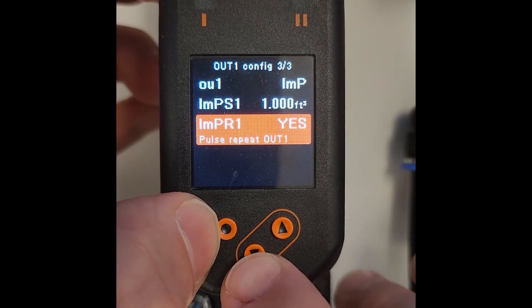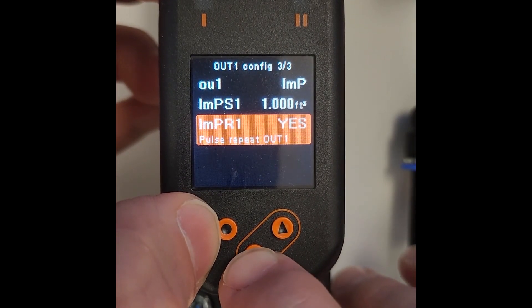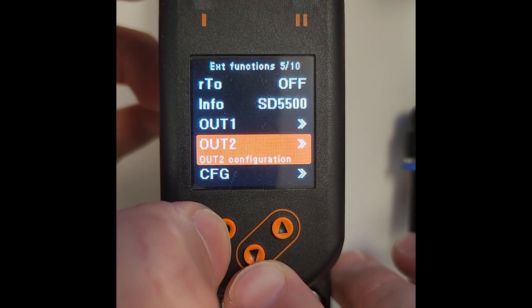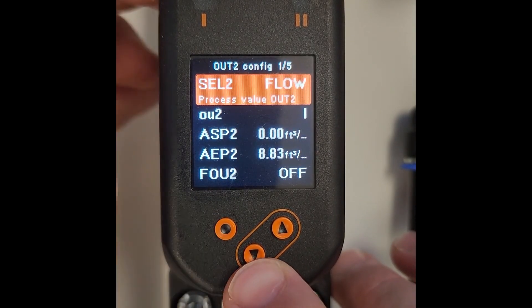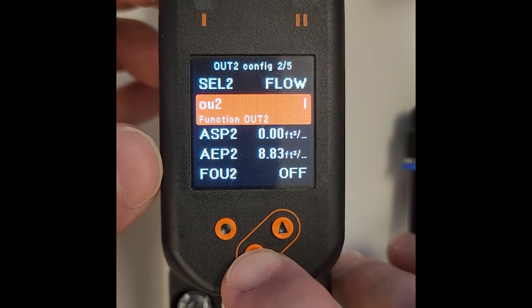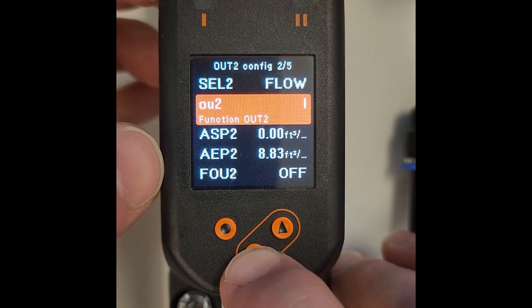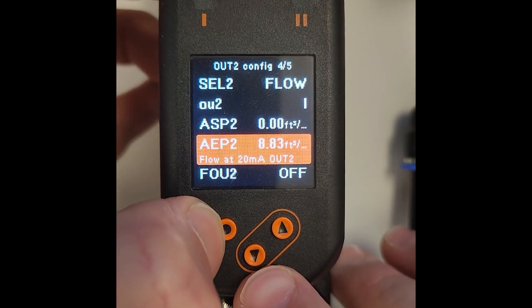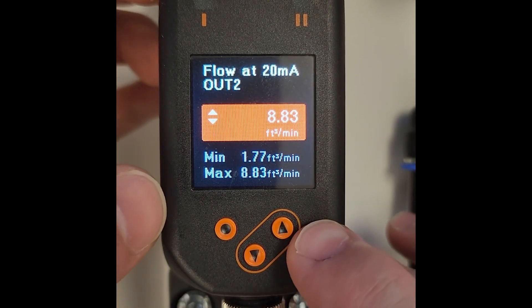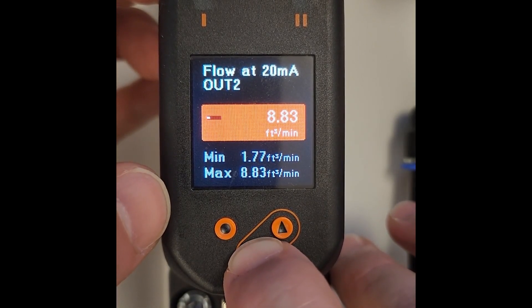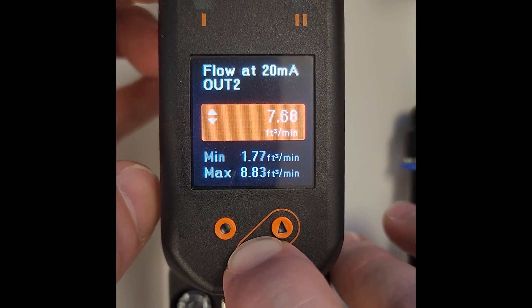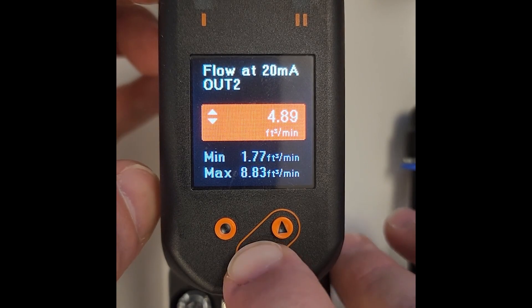IMPR1 is automatically set for yes, so we get that pulse signal. At OUT2 you will make sure that OU2 is set for I for current. ASP is typically zero. If you go into AEP you can scale that analog endpoint which will be your 20 milliamp signal. In this case I am going to use the down button to scroll and press enter once at 5.